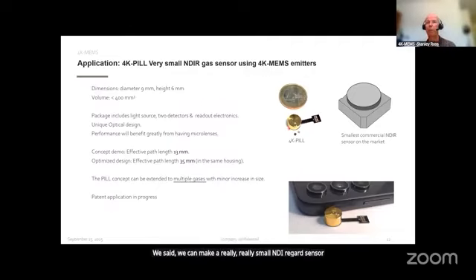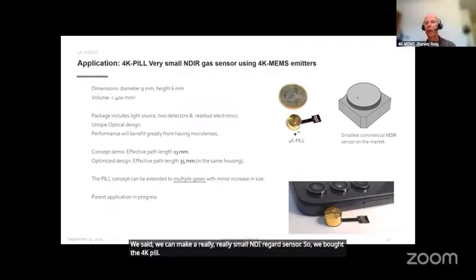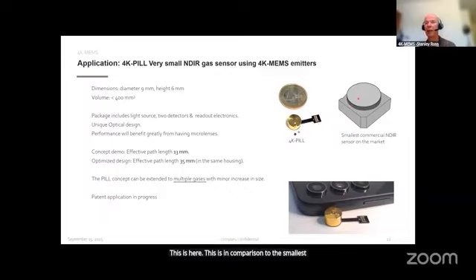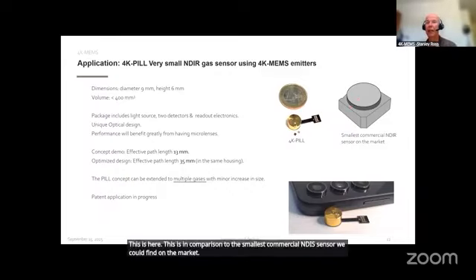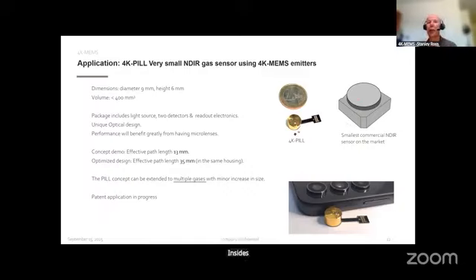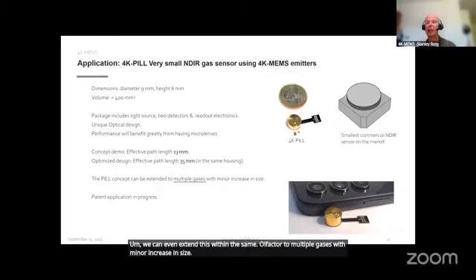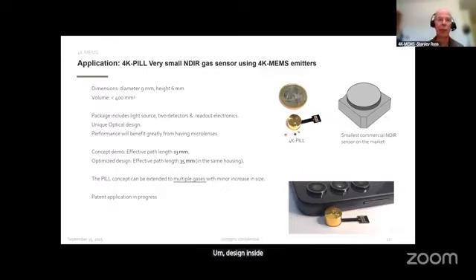So we call it the 4K pill. This is here. This is in comparison to the smallest commercial NDIR sensor we could find on the market. Inside is our emitter, 2 detectors, 2 filters, readout electronics. And we get performance similar to standard NDIR systems. We can even extend this within the same form factor to multiple gases with minor increase in size. The design inside, I can't show you its unique optical design. We're actually submitting the patent on it tomorrow.